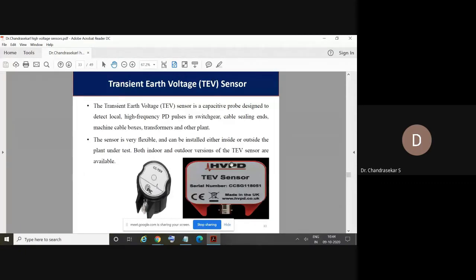So another type of sensor is a transient earth voltage sensor. So this is actually like a capacitive probe. Okay, it is used to detect the high frequency PD pulses. This is also mainly used for all high voltage switchgears and transformers and cables.